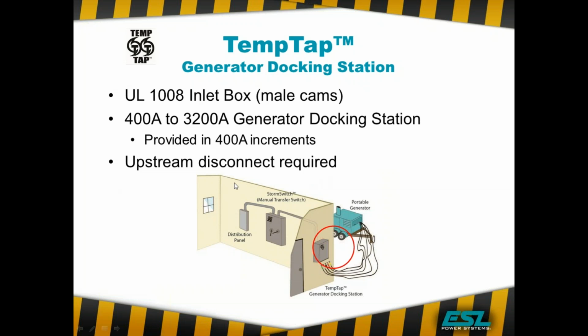And you just need some sort of upstream disconnect, whether it's a manual transfer switch, an ATS, switchgear, some way to make sure this portable generator isn't on at the same time as your other source, whether it be utility or another generator or UPS system, whatever it might be. But it's just a docking station, no breakers, although you can get this with a breaker in it and Kirk lock if necessary.